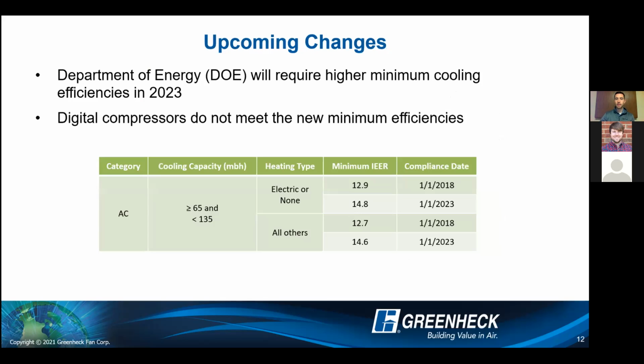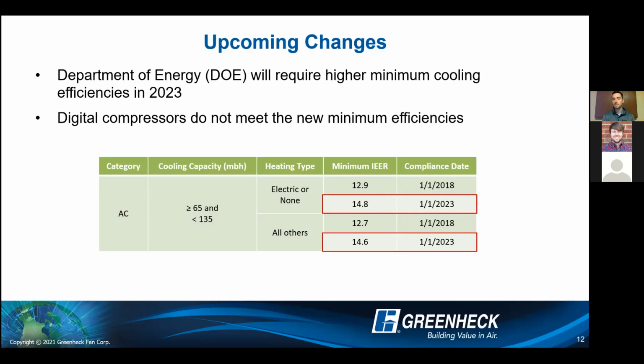On a side note, with the inverter compressor and digital compressor as well, there are a number of changes that are happening. I believe I briefly mentioned it, but the Department of Energy will require higher minimum cooling efficiencies in that 2023 timeframe. And with these minimum efficiencies, as you can see in the screenshot below, they jump up pretty substantially compared to what used to be in the compliance date. So digital compressors will not meet those new minimum efficiencies. So as you're thinking about new projects coming out, or maybe you've always used digital but you're curious about inverter, now is a great time to start looking at those variable speed compressors, because that is really where the direction of this type of equipment is going. And all manufacturers are going to have to switch to pretty much standardizing inverter compressors.